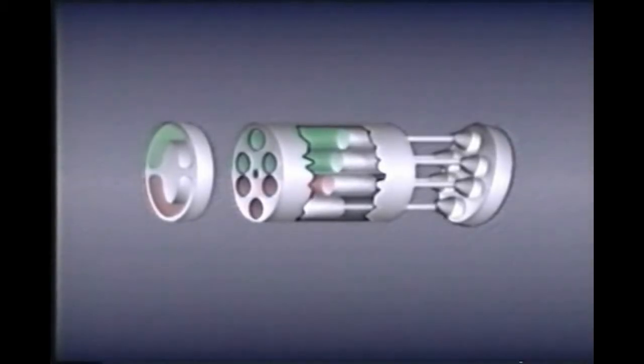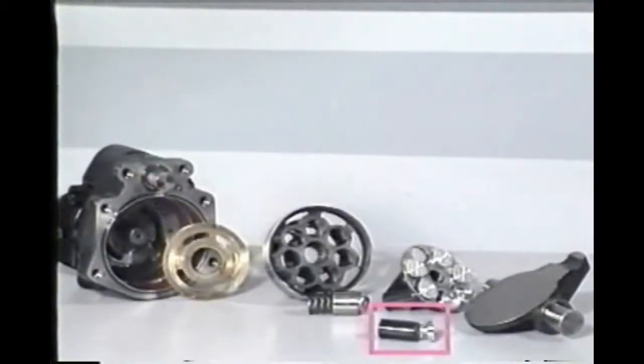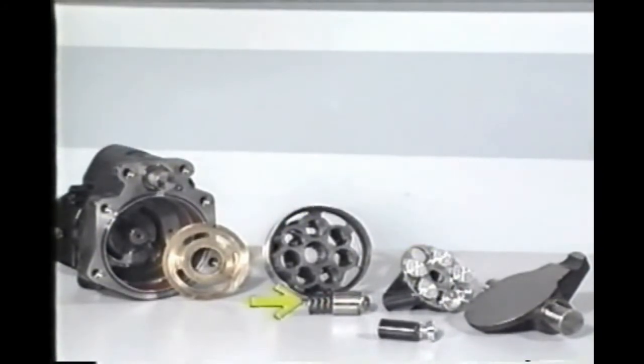The axial piston pump also has pistons, but these fit into piston bores in a cylinder barrel. A shoe plate and a bias spring hold the piston shoes against a plate called a swash plate. The pump's inlet and outlet are through a port plate at one end. In operation, everything but the swash plate and the port plate rotate with the shaft.